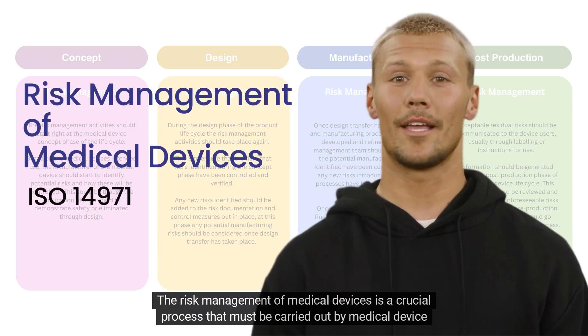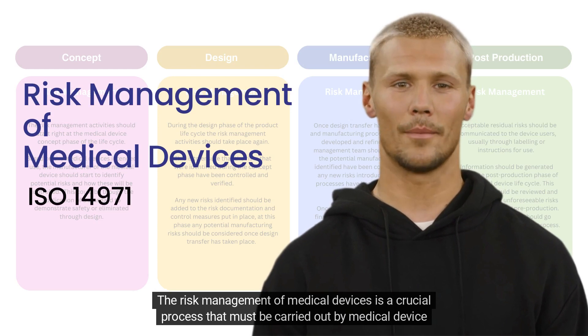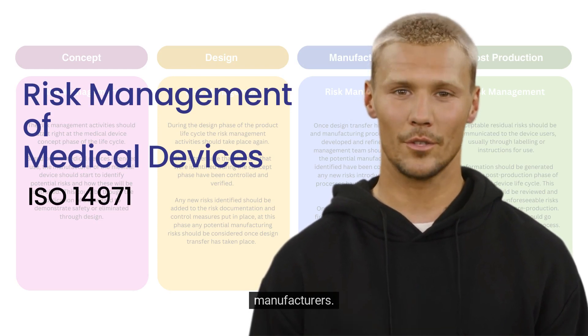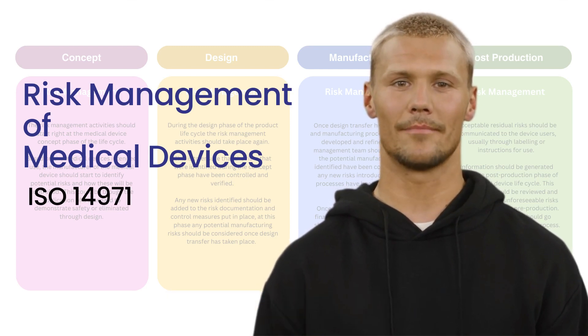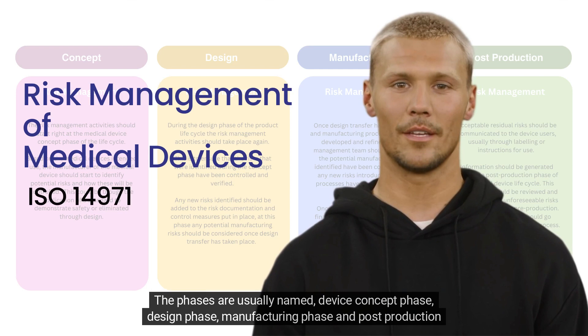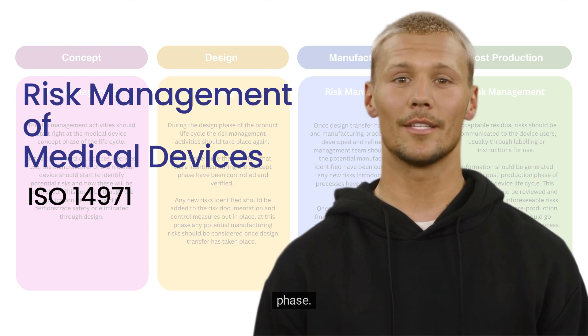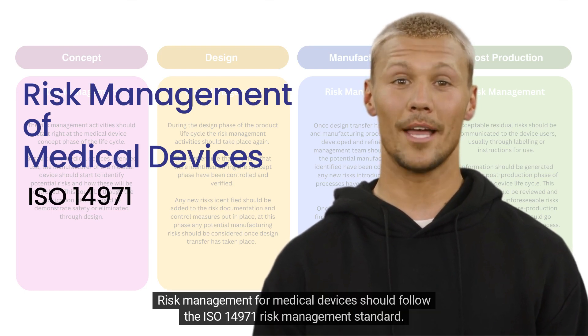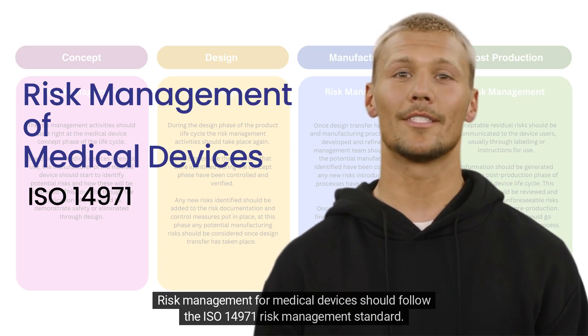The risk management of medical devices is a crucial process that must be carried out by medical device manufacturers. Risk management should be performed at each phase of the life cycle of the medical device. The phases are usually named device concept phase, design phase, manufacturing phase, and post-production phase. Risk management for medical devices should follow the ISO 14,971 risk management standard.